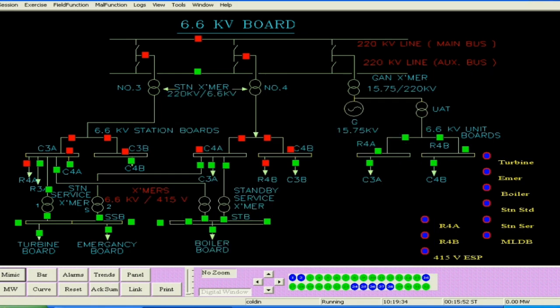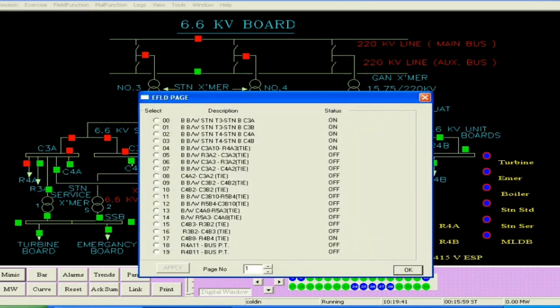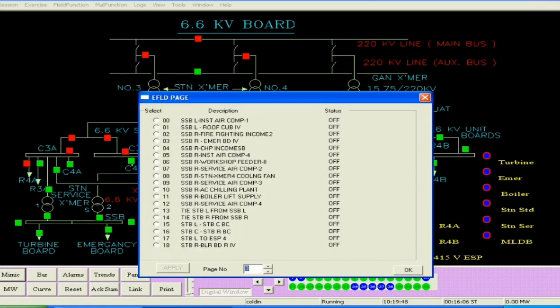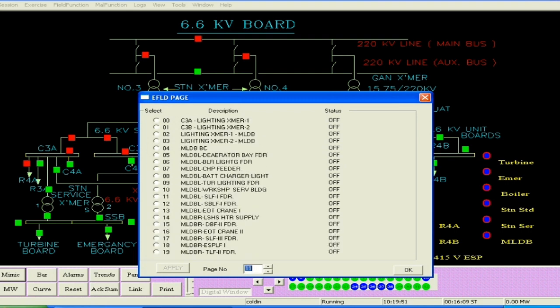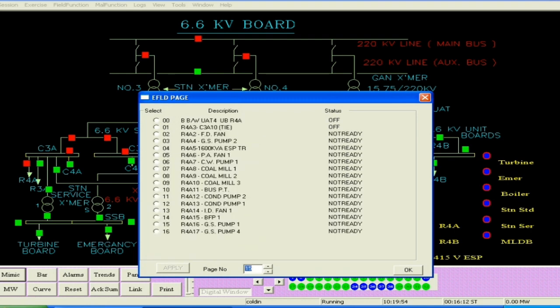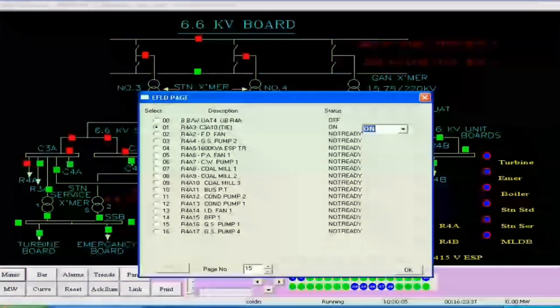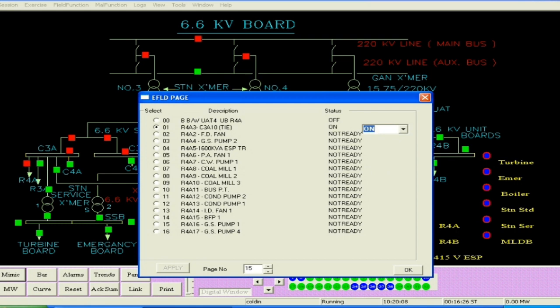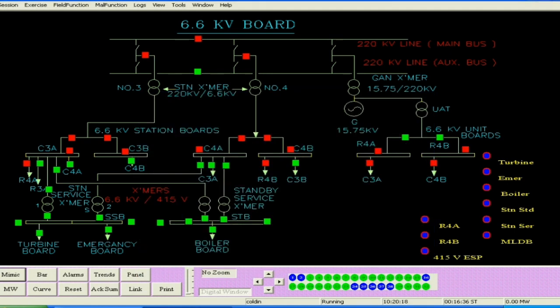So we go to page number 15 now. There again R4A3 to C3A10, means from station to R4A we will make that breaker also on, so that R4A will be charged. Similarly, we go to page number 16. There also, index number 1, we close the tie so that R4B is also charged. So once these two are charged, we have charged the unit 6.6 kV boards, that is R4A and R4B, and you can see all the breakers going in red, those are being charged.